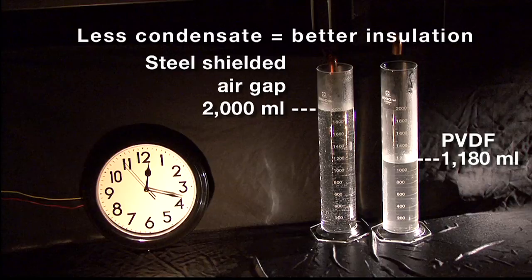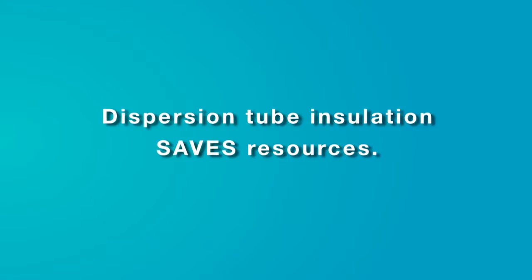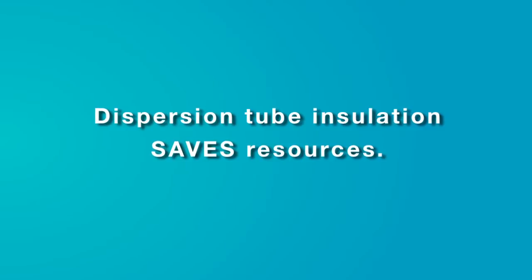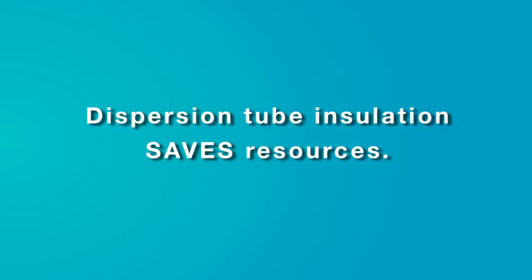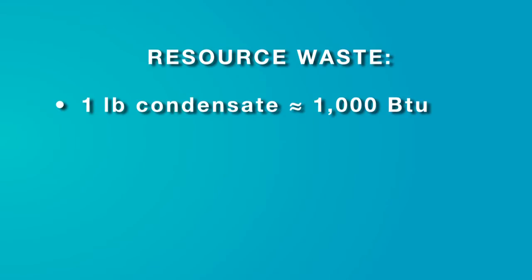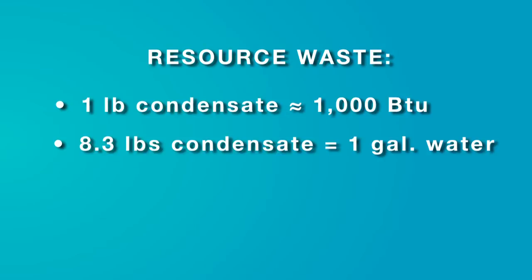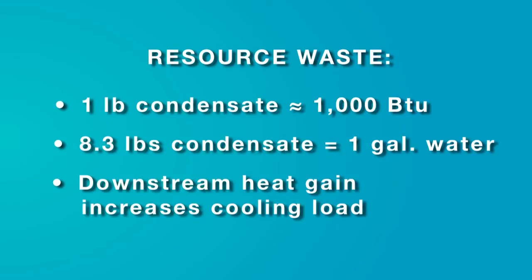Why are the results of this test so important? Because unnecessary heat gain and condensate production wastes energy and water. Every pound of condensate produced wastes about 1,000 BTUs. That's the energy originally used to change that pound of water into steam humidification. And every 8.3 pounds of condensate sent to a drain wastes a gallon of water. And downstream heat gain increases the cooling load.